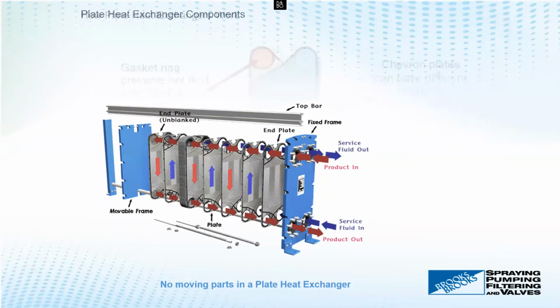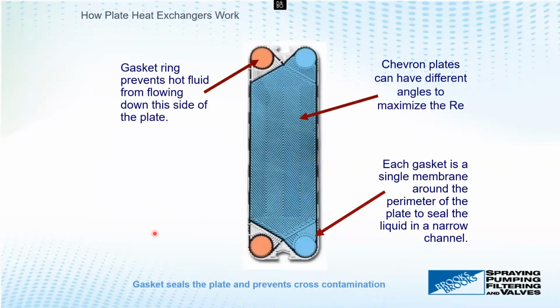Pretty simple. The magic of a heat exchanger, and a plate and frame heat exchanger specifically, is the corrugations on the plates, designed to give the most heat exchange units. These corrugations can be done at different angles, which we'll talk about in a minute. They're all designed to remove heat specific to your application, your flows, your fluids. We can change these things to maximize the heat exchange given the differential pressure you're allowed to have, the viscosity, or whatever other process variables we have to take into account.